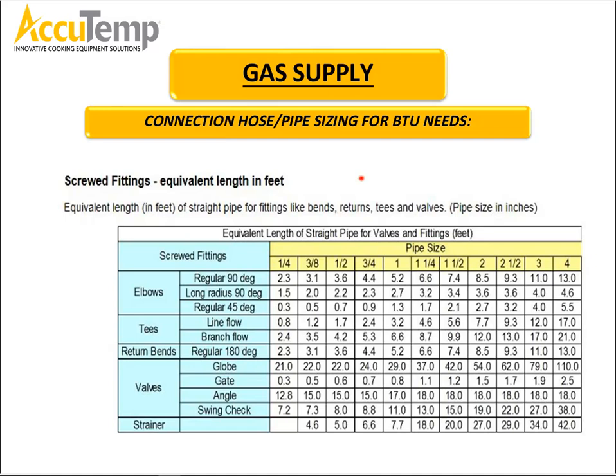All right, just as with the length of pipe, each fitting also equals a particular length in feet. Let's say, for example, we have a regular 90-degree fitting. Once again, we're going to go back to our 1-inch diameter pipe. That 90-degree fitting will equal 5.2 feet. In other words, you could stretch that 90-degree fitting to 5.2 feet in length.